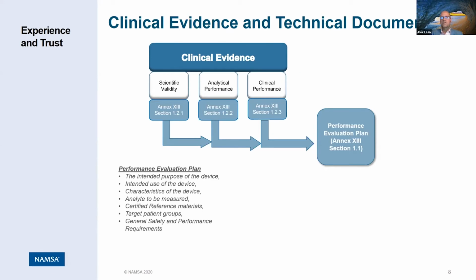The performance evaluation plan is not necessarily your performance evaluation procedure. The procedure is typically a document that's part of your QMS and will describe the general process of how you obtain clinical evidence. It doesn't tell you much about how you obtain clinical evidence for that specific device. And that's basically where the performance evaluation plan comes in. Again, scientific validity, analytical performance, and clinical performance need to be described. What is your strategy? How do you want to achieve the intended purpose? How do you want to demonstrate the intended purpose? That all needs to be defined in your performance evaluation plan. The plan can be quite simple for a simple device, and can also be quite complicated for a very new, novel device, which may have a lot of functions.